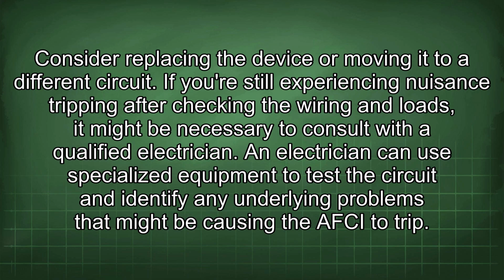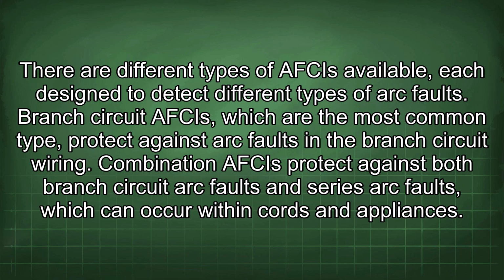If you're still experiencing nuisance tripping after checking the wiring and loads, it might be necessary to consult with a qualified electrician. An electrician can use specialized equipment to test the circuit and identify any underlying problems that might be causing the AFCI to trip. There are different types of AFCIs available, each designed to detect different types of arc faults. Branch circuit AFCIs, which are the most common type, protect against arc faults in the branch circuit wiring. Combination AFCIs protect against both branch circuit arc faults and series arc faults, which can occur within cords and appliances.